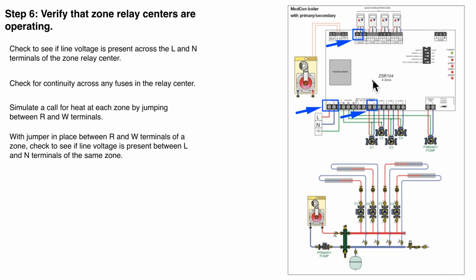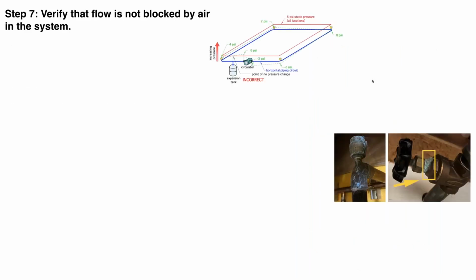So you can see as we're working our way through these steps, we're basically starting with power available, and then we're working through what is supposed to happen. Thermostat calls for heat, zone relay panel responds, turns on a circulator, and so forth. Now, verify that flow is not blocked by air in the system. There's a lot of things that can cause this. One of the classic ones is a circulator that is pumping towards the expansion tank and has a system effect where we're going to negative pressure in parts of the system. We're actually pulling the pressure in some portions of the system below atmospheric pressure.